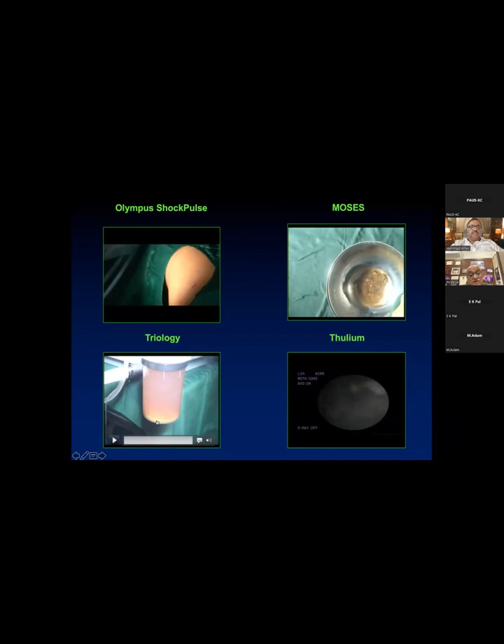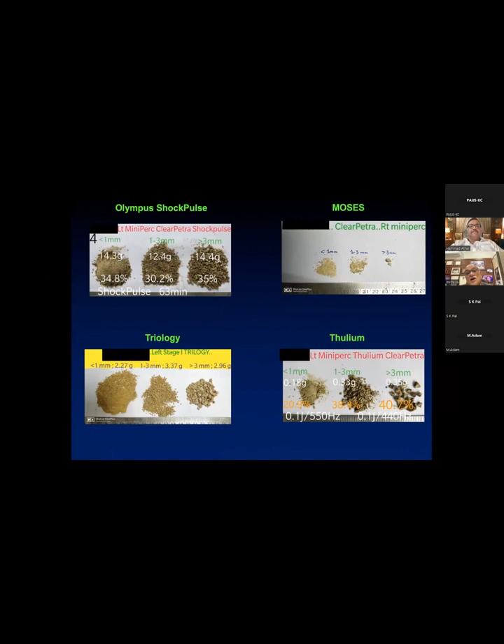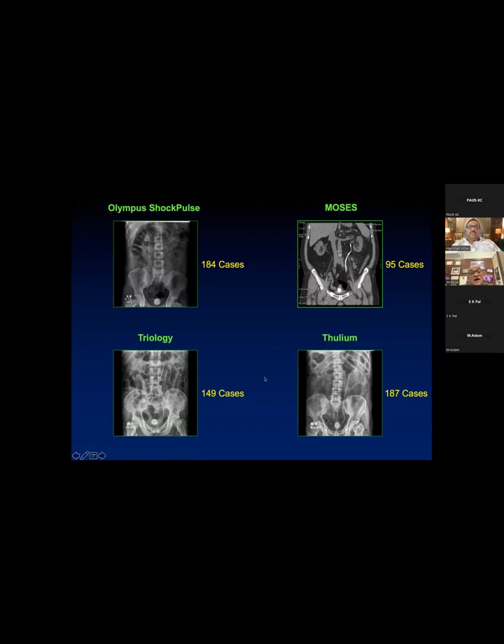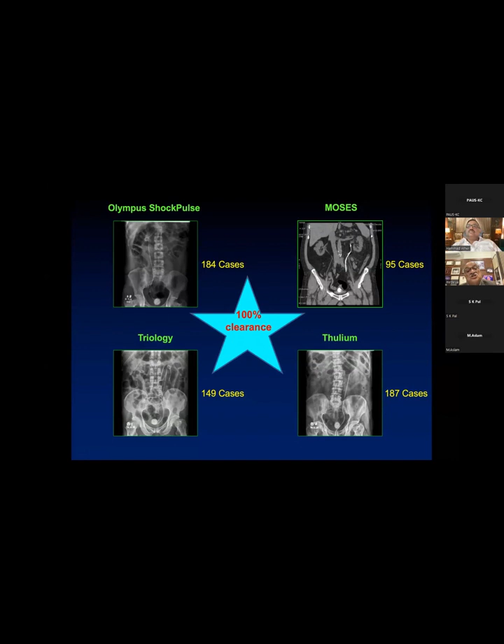So you can see with the trilogy that the dust is very fine. Again, in a ClearPetra or in a thulium, you can see the dust is very fine. And here the fragmentation is good. So we have divided and tried to find out how we can do it. With suction, you can reduce the time of fragmentation and clearing the stone. We have done a significant number of cases in each arm, and we found that at the end of the procedure we could achieve 100% clearance of the stone. And we did a CT scan after 48 hours. So we could do that.